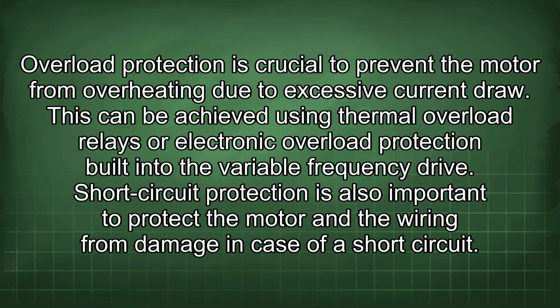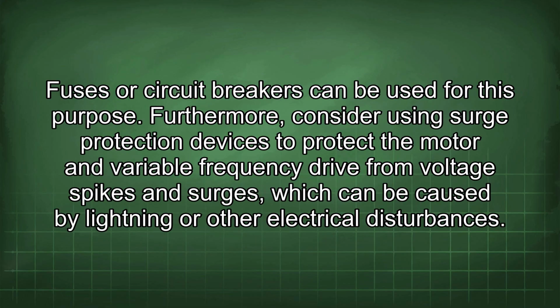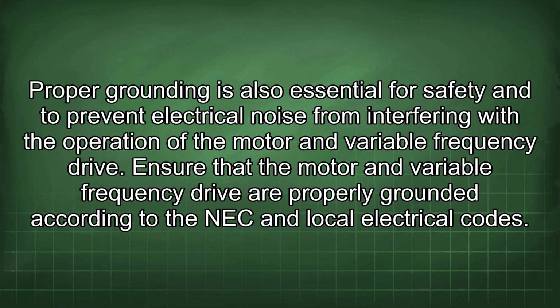Short circuit protection is also important to protect the motor and the wiring from damage in case of a short circuit. Fuses or circuit breakers can be used for this purpose. Furthermore, consider using surge protection devices to protect the motor and variable frequency drive from voltage spikes and surges, which can be caused by lightning or other electrical disturbances. Proper grounding is also essential for safety and to prevent electrical noise from interfering with the operation of the motor and variable frequency drive.